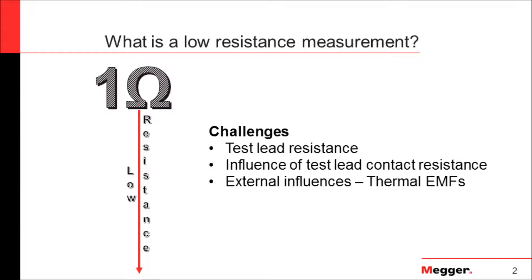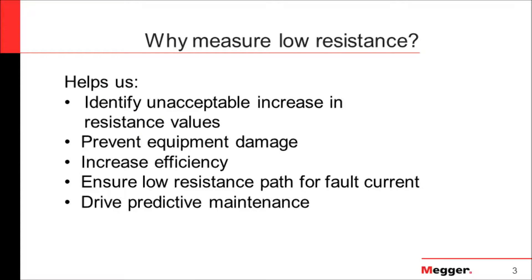So those are some of the challenges we will face when making these measurements. Now that we know what a low resistance measurement is, you may be wondering: why should I measure this? If we recall from Ohm's law, for a specified energy source operating at either AC or DC voltage, the amount of current drawn depends upon the resistance of the circuit or component. Identifying resistance elements that have increased above an acceptable value will help us prevent long-term damage to our equipment, minimize energy wasted as heat, and ultimately ensure maximum efficiency of electrical components.